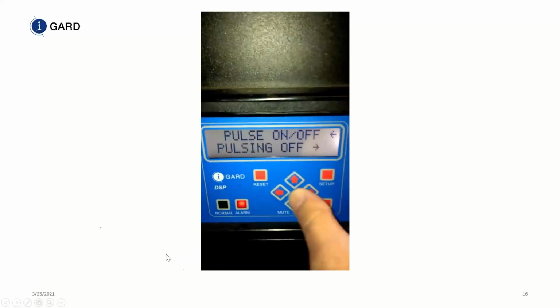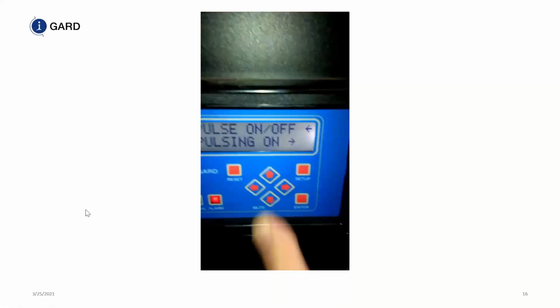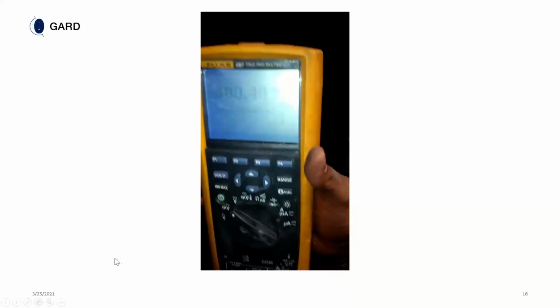I'm going to turn on the pulsing on this system. That's a three-decade experienced thumb pressing that button, okay? So we're going to turn on the pulsing. And what's important here is try not to pay attention to the digital number. I understand we're all engineers. We want to focus on that digital number because we think it's more accurate than anything else out there. Try not to look at that digital number because you'll drive yourself nuts. Instead, look at this bar graph underneath the digital number and you'll see it moving at the same rate that we're pulsing or changing the value of that resistor. That's telling us that the fault is downstream from our location.